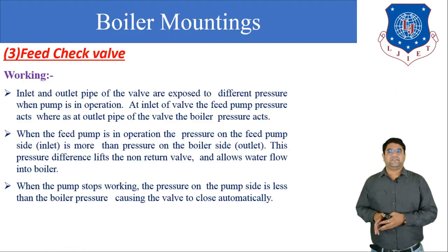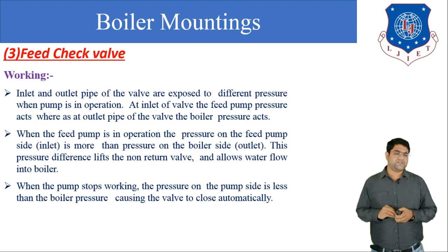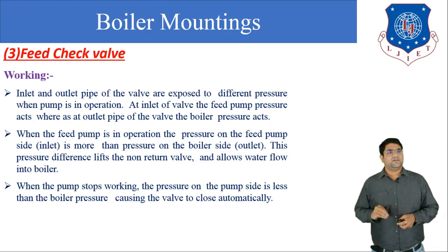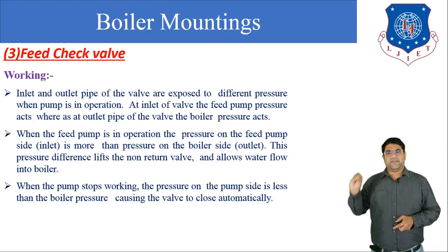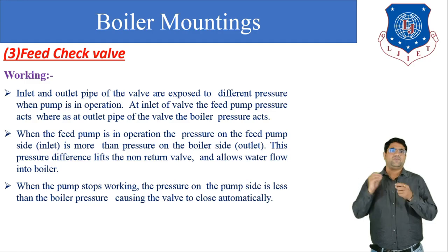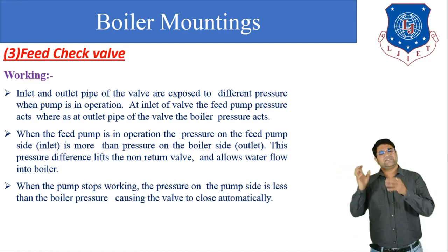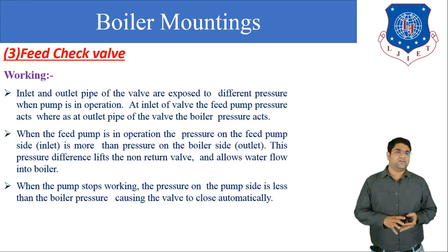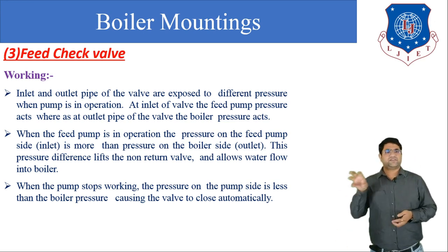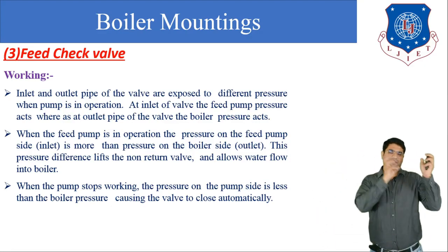So here we can write that the inlet and the outlet pipe of the valve are exposed to different pressures when the pump is in operation. At the inlet of the valve, the feed pump pressure acts, whereas at the outlet pipe, the boiler pressure acts. Now when the feed pump is in operation, the pressure of the feed pump, or the pressure at the inlet, is higher than the pressure of the boiler. And due to this pressure difference, the water will flow from the inlet side to the outlet side.